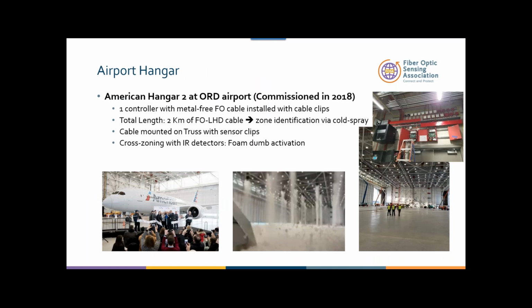Another application is airport hangar. Hangars are very interesting in the sense that the asset that we're monitoring is probably as expensive as we can get. Here's an example of an airport hangar in Chicago. You have one system that's monitoring up to 2 kilometers mounted on the roof, and tied in on the picture on the right, you actually can see the fiber optic linear detection controller tied into the fire panel. It's very, very important. On the bottom left, you can see why this is such a critical asset.